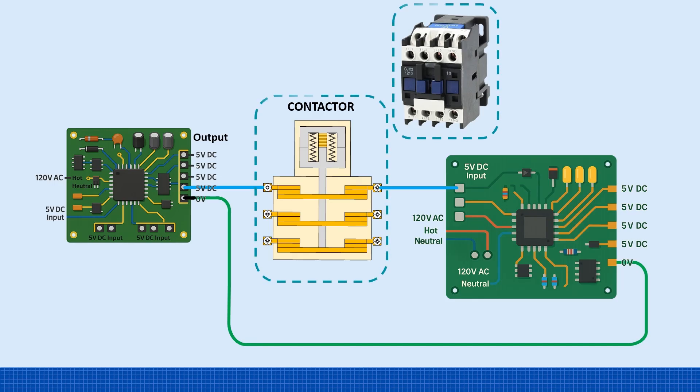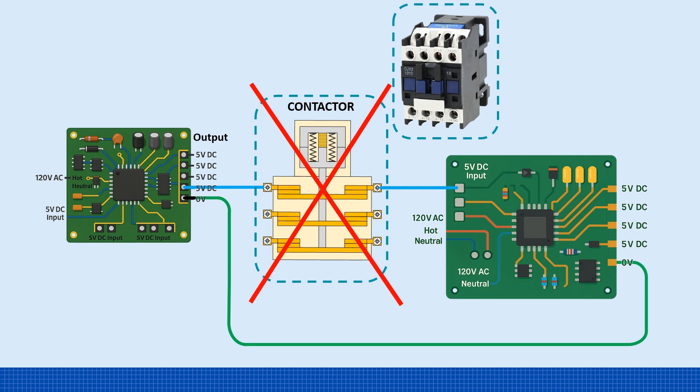The problem is, contactors aren't built for low-voltage DC. Even though they're enclosed, they're not sealed. So, over time, dust and oxidation accumulate on the contacts. With such small DC currents, it doesn't take long before the signal can't pass through reliably, leading to control failure.